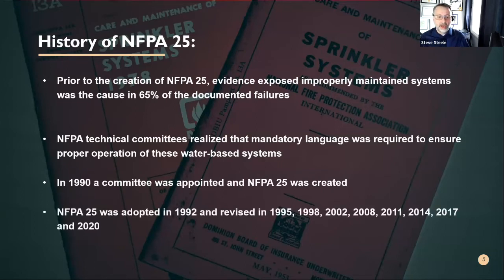So in 1992 we did officially get, and again, this is not going back too long ago, NFPA 25 adopted in 1992, and those are the cycles or revisions that we stand at now, with 2020 being the most current. These dates are important because we will be looking at some of the differences between NFPA 25 and the Ontario Fire Code. Historically, the adoption of the Ontario Fire Code was in the early 80s, somewhere around that time. This is pre-NFPA 25 we're talking about.